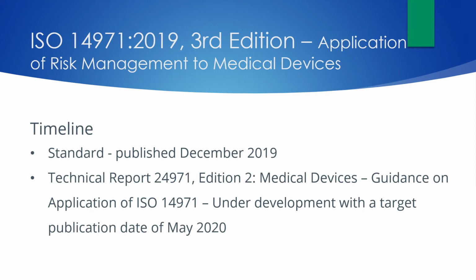The updated ISO 14971 standard was published in December of 2019. There is a target publication date of May 2020 for its accompanying technical report 24971, which is the guidance on the application of the standard 14971. Informative annexes will primarily reside in this technical report because it's easier to update a technical report than the entire standard. Technical Report 24971 is a necessary supplement which contains guidance on hazard identification, risk concepts and techniques, risk management for in vitro diagnostic devices, and risk management plans.